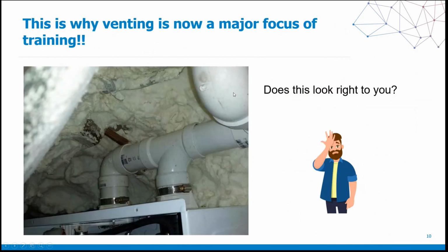And when we talk about venting, we also need to talk about the issues with venting. So the manufacturers think it's wonderful that we're now doing combustion testing. It's great. However, they're also realizing as a byproduct of that we're also venting their appliances incorrectly. Now, I don't want you to look at this slide and joke and say to yourself, wow, this was done for efficiency. No, it was not. When you vent something this way, when you tie in your supply and exhaust air into the same conduit, you're creating a potentially dangerous and hazardous condition for all those that are occupying that space. And that is why predominantly now, 9 out of the 10 manufacturers that are putting on classes for their equipment are actually instructing you on how to vent it properly because of issues like this here.